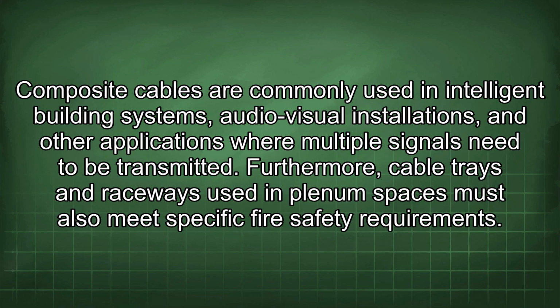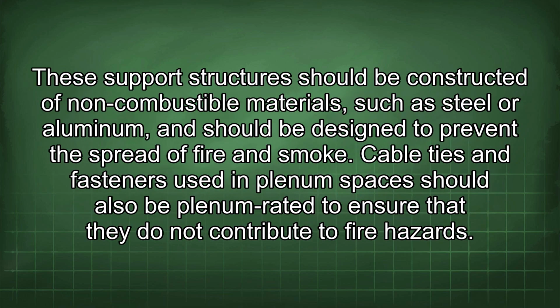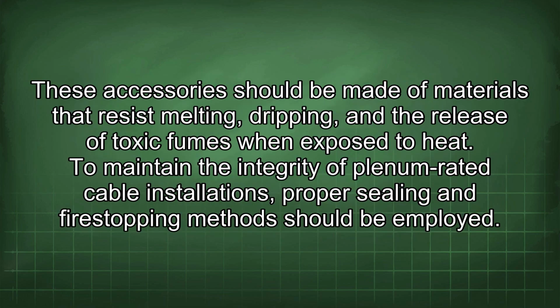Furthermore, cable trays and raceways used in plenum spaces must also meet specific fire safety requirements. These support structures should be constructed of non-combustible materials such as steel or aluminum and should be designed to prevent the spread of fire and smoke. Cable ties and fasteners used in plenum spaces should also be plenum rated to ensure that they do not contribute to fire hazards. These accessories should be made of materials that resist melting, dripping, and the release of toxic fumes when exposed to heat.